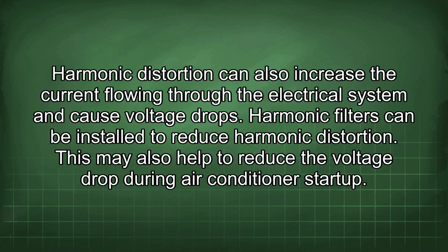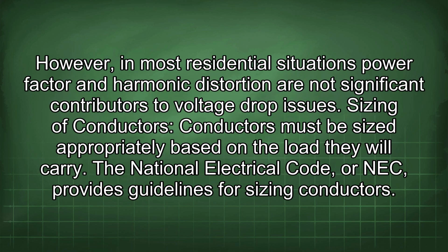This may also help to reduce the voltage drop during air conditioner startup. However, in most residential situations, power factor and harmonic distortion are not significant contributors to voltage drop issues. Sizing of conductors. Conductors must be sized appropriately based on the load they will carry.